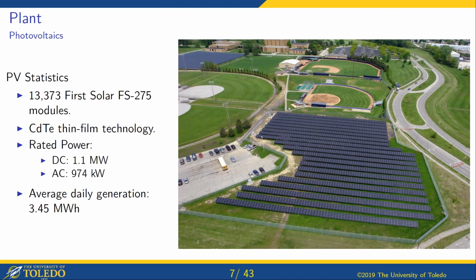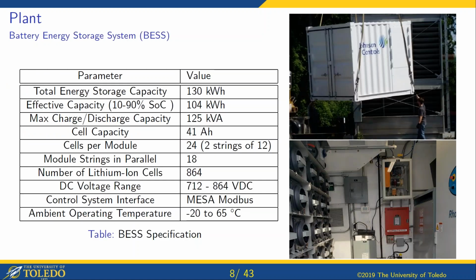The photovoltaic arrays are cadmium telluride panels from First Solar, a local company here in Toledo - well, they're actually based in Tempe now, but their manufacturing is still here in Toledo, and they started on our campus. The rated power is 1.1 megawatts DC, or just under a megawatt AC, with average daily generation of 3.45 megawatt hours.